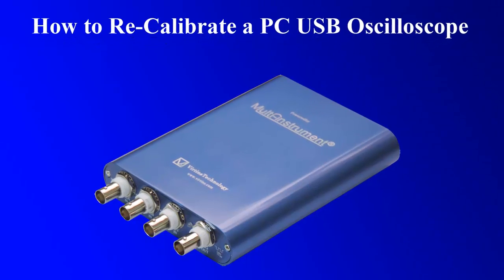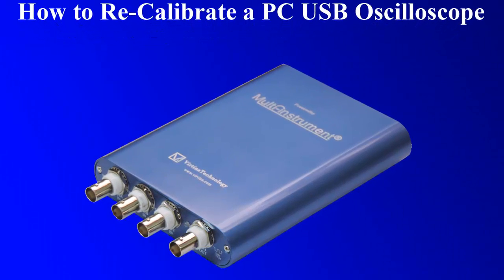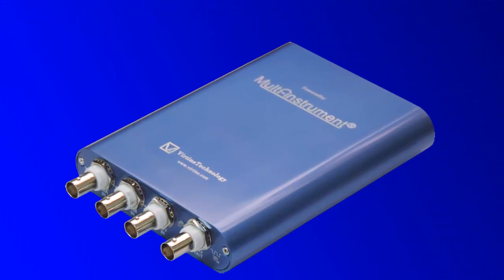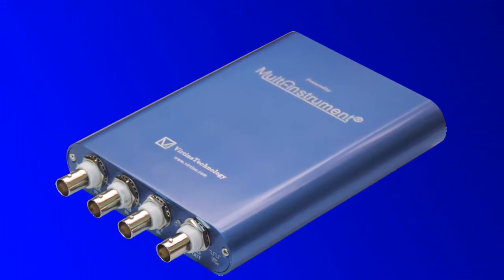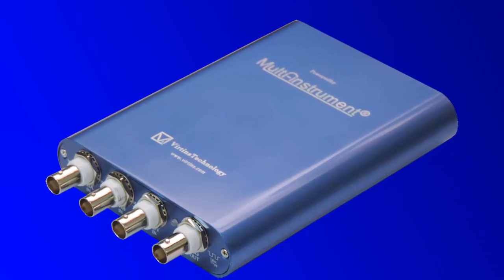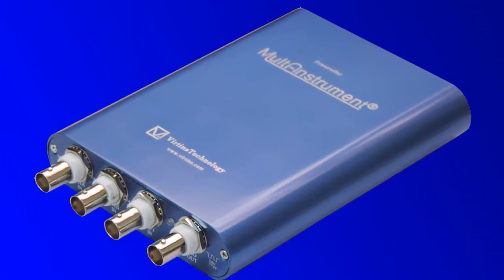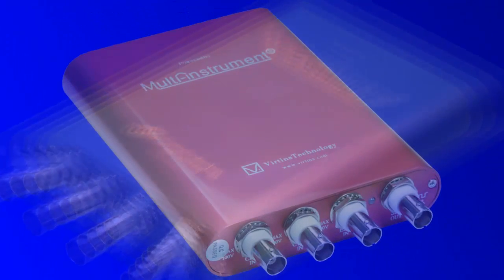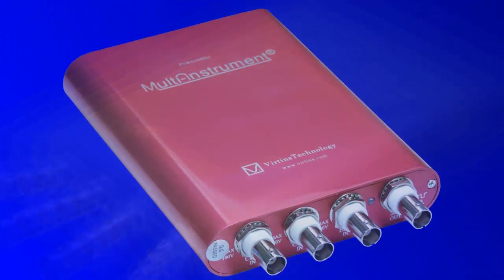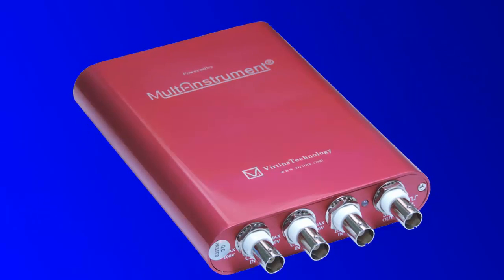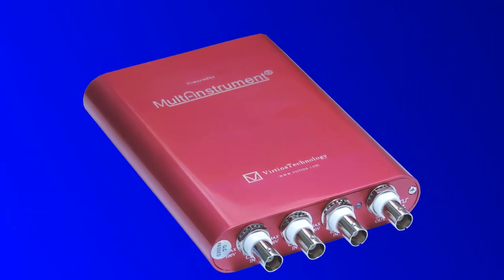Here we would like to demonstrate how to recalibrate a PC USB oscilloscope. The second-generation PC USB oscilloscopes from Virtins Technology support recalibration. Recalibration is generally not required for a VT DSO, but if your organization standard requires it to be recalibrated on a regular basis, then it can be done. The recalibration includes gain and offset adjustment for each voltage measuring range of each input channel.